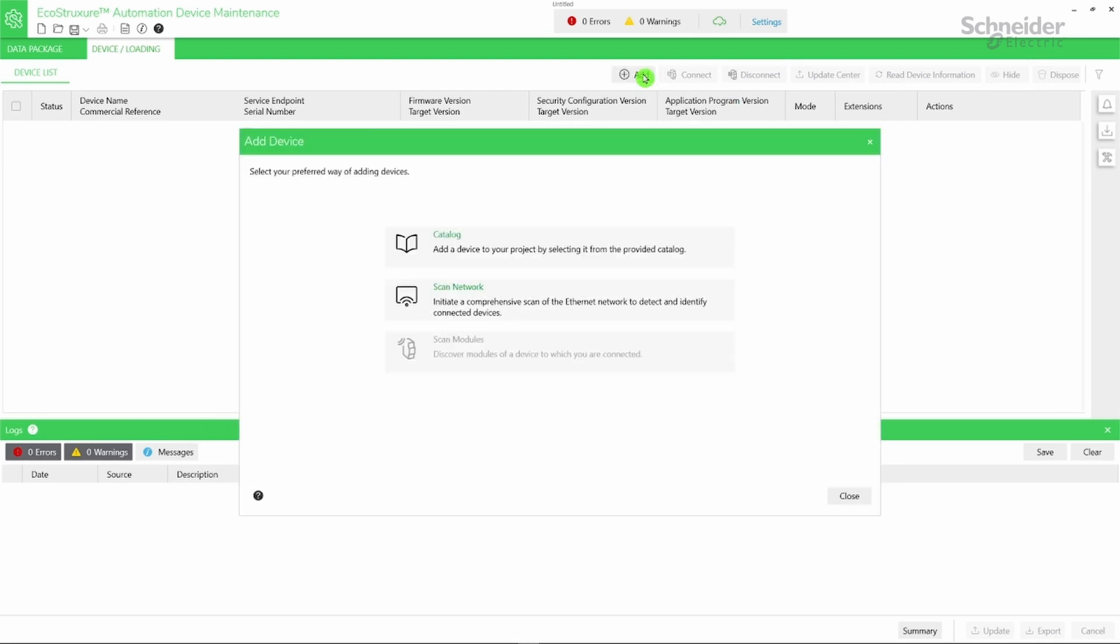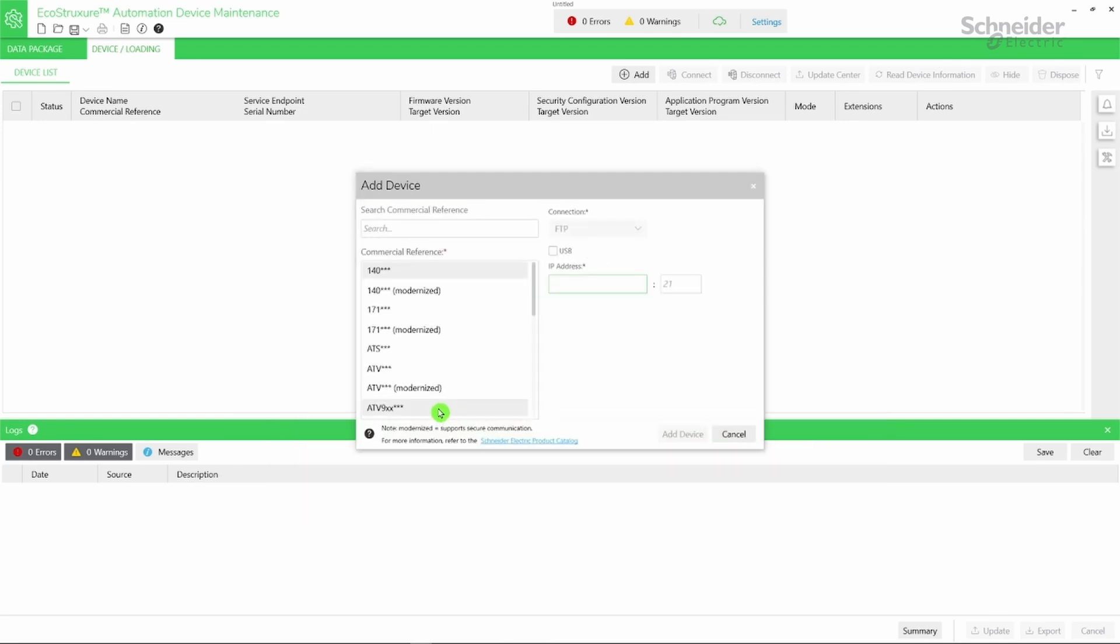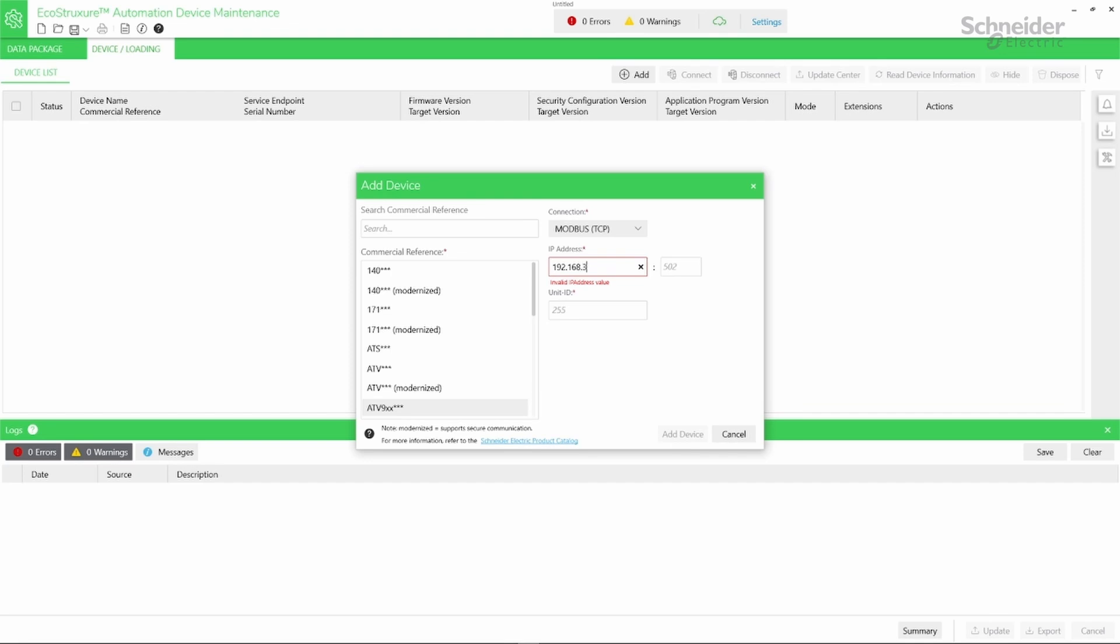To add your device using an Ethernet cable, click the add icon, select Catalog. Select the commercial reference of your device. Ensure that Modbus TCP is selected as the connection type. Type the IP address of your device. Ensure that the IP address of your device is in the same subnetwork as the IP address of your PC. And finally, click Add Device.